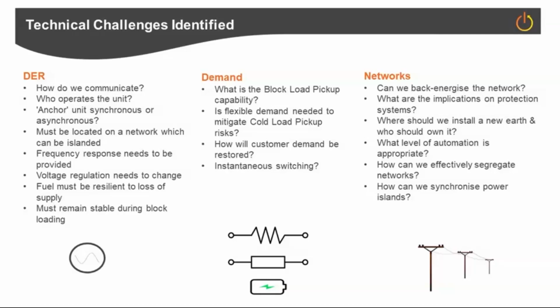There's this concept called cold load pickup. This is when you are restoring demand from blackout. You don't necessarily know how much demand you're going to get. It could be up to 1.5 or 2 times what you saw prior to blackout. So this cold load pickup risk presents a big risk to a generator and its stability. Is there a way to mitigate that? Can you use flexible demand, a load bank or a battery or something like that? We'll come back to that a bit later as well.